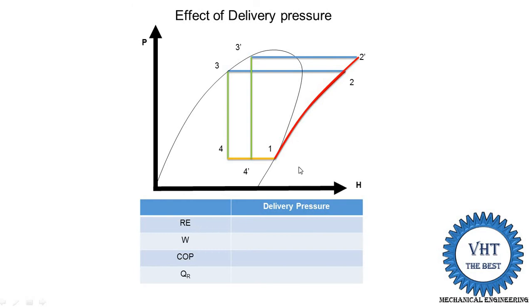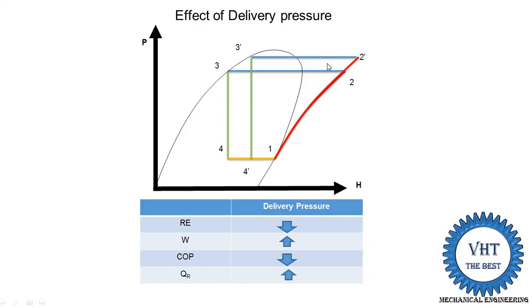For delivery pressure: refrigerating effect is reduced because H1 minus H4-dash is a smaller line than H1 minus H4. Work done is increased because H2-dash is greater than H2, so H2-dash minus H1 is larger. COP equals refrigerating effect divided by work done — refrigerating effect is reduced and work done is increased, so COP is reduced. Heat rejection is also increased because at the higher pressure region a higher mass flow rate is required, demanding more air or water for cooling. So increasing delivery pressure reduces system performance.